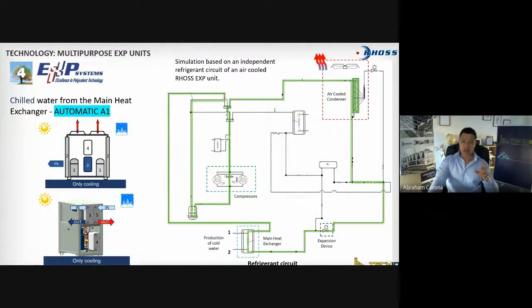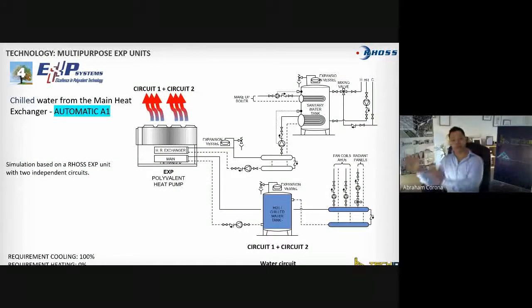But how would that look on the actual water side? In this simulation we're doing now, this is a generic water connection with all the valves. We're using a chiller EXP with 2 circuits. Let's imagine that. You see the requirement on the bottom left. There is 100% demand of cooling, 0% demand of heating. In that moment, we're working as a standard chiller. Both circuits are cooling the water, and we're rejecting the heat via the air-cooled condenser. Looks pretty simple now. Right?